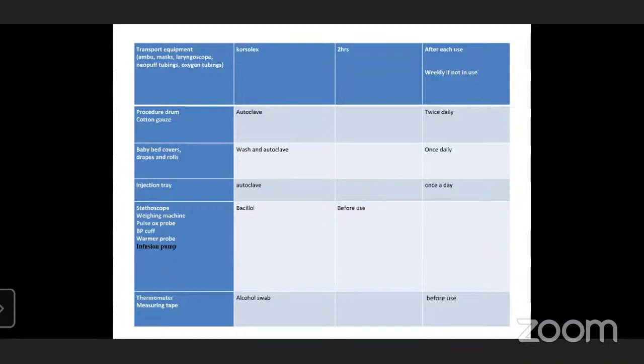The other thing that needs cleaning is the MR humidifier, a very common equipment used in the NICU for any baby on ventilator or CPAP support - not the top part, which is sent for autoclaving or gas sterilization along with the tubings, but the humidifier base, which you still need to clean with 0.5% bacillocid every 72 hours. Basically there are two disinfectants we use in this presentation.